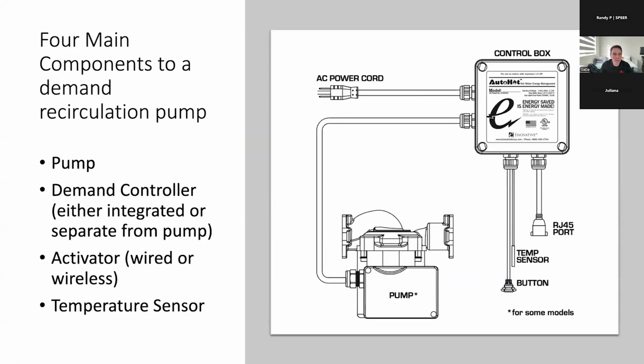So there are four main components to a demand recirculation system. You have the pump, you have the controller, which can be either integrated into the pump or separate from the pump. You have an activator, which can be wired or wireless, and then you have a temperature sensor.